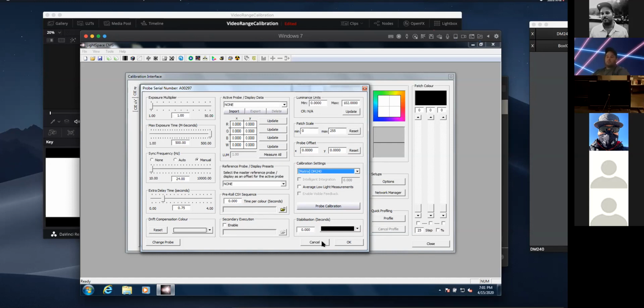How necessary the timing of that is depends a lot on the particular colorimeter you're using. Some are way more stable over time than others, but it depends a lot on whether they're using glass filters or gel filters, and whether they're well sealed or not. But all probes drift, so they do need to be recertified and recalibrated.